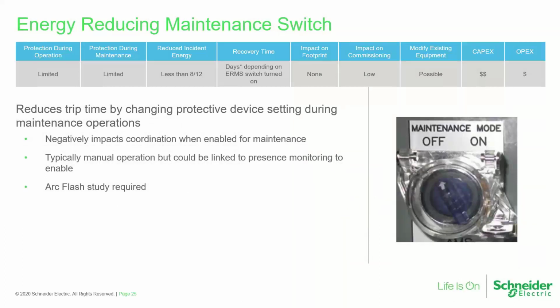The maintenance switch, again, is maybe one of the most popular, if not the most popular, reduction solutions. We're saying protection during operation and maintenance is both limited. Why is it limited? You're getting protection for downstream equipment. I've seen people who firmly believe that, okay, I've got this feeder breaker here in this switchboard, and if I turn the maintenance switch on, now I can do whatever I need to. I can rack this breaker out or do whatever, and I'm protected. No, you're protected downstream. You've got to understand where that protection actually is.